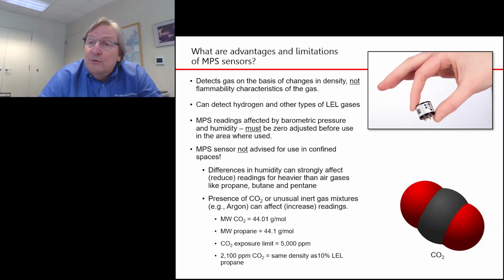It turns out that if you have an oxygen deficiency, most of the time the oxygen deficiency is due to the presence of carbon dioxide. The exposure limit for carbon dioxide is 5,000 parts per million. That's the 8-hour TWA. Well, if you have 2,100 parts per million of CO2, that's not even one half the TLV, not even one half the permissible exposure limit for carbon dioxide. That is the same exact density as 10% LEL propane. So you can see how that can cancel out the ability to pick up a lighter than air gas, or if you have carbon dioxide along with some heavier than air gas, your reading is going to be inaccurately high. So high or low, you can easily have an erroneous reading.